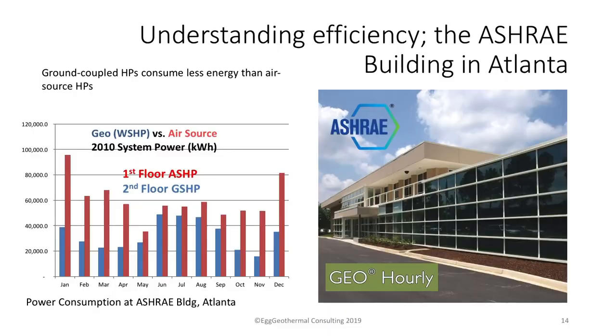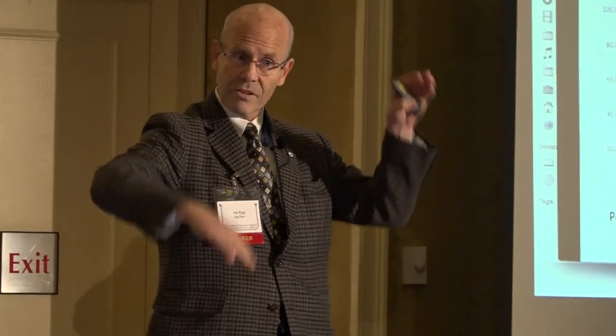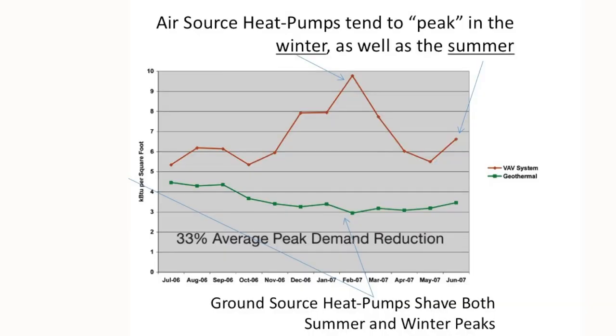Ground source heat pumps, as shown in the ASHRAE building in Atlanta, were installed on the first floor with air source heat pumps and the second floor with geothermal heat pumps. When it gets really cold outside, the air source heat pumps can do the job, but efficiency peaks out during that time. As you can see by the red and blue lines, the geothermal heat pump has an unfair advantage: the ground is the same temperature year-round, where air temperature fluctuates seasonally and changes the efficiency.